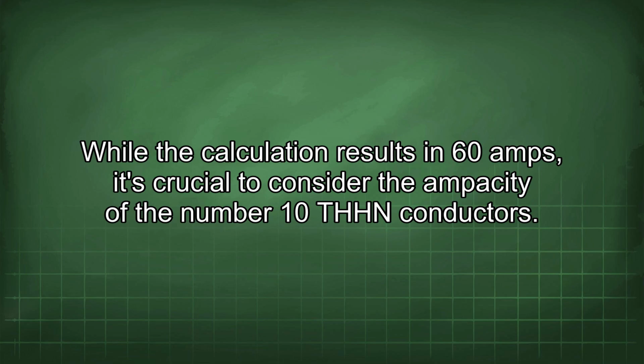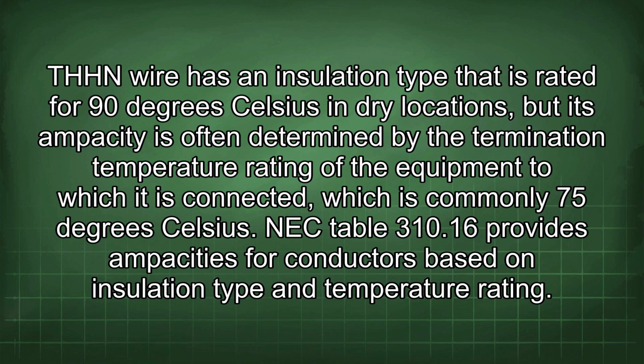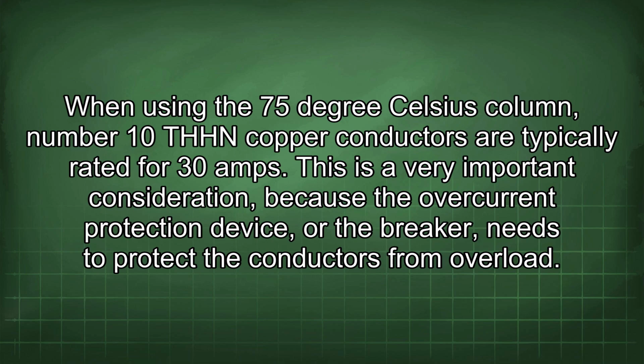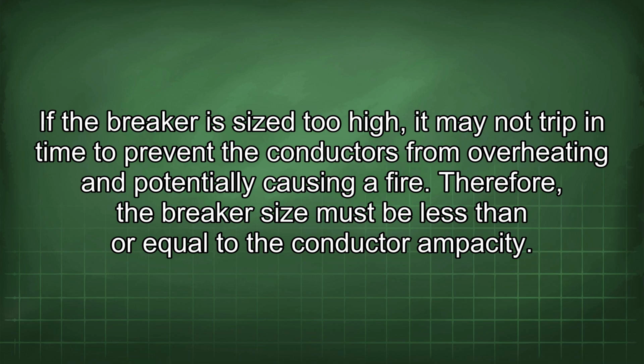While the calculation results in 60 amps, it's crucial to consider the ampacity of the number 10 THHN conductors. THHN wire has an insulation type that is rated for 90 degrees Celsius in dry locations, but its ampacity is often determined by the termination temperature rating of the equipment to which it is connected, which is commonly 75 degrees Celsius. NEC Table 310.16 provides ampacities for conductors based on insulation type and temperature rating. When using the 75 degrees Celsius column, number 10 THHN copper conductors are typically rated for 30 amps. This is a very important consideration because the overcurrent protection device, or the breaker, needs to protect the conductors from overload. If the breaker is sized too high, it may not trip in time to prevent the conductors from overheating and potentially causing a fire.